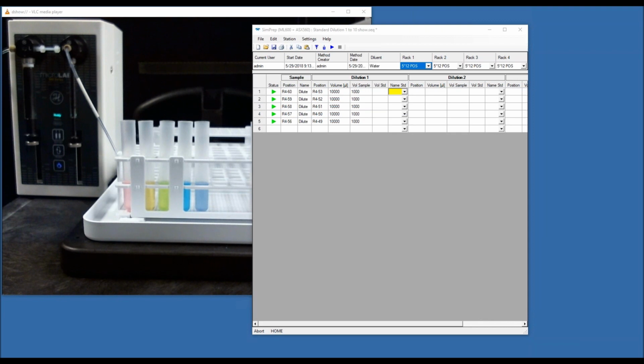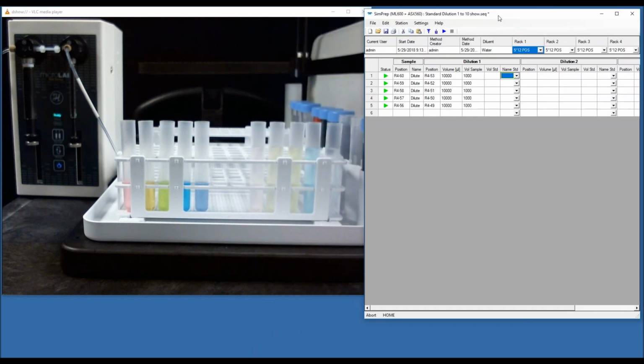Another question is, what is the time per sample? This is a pretty common question, and it really varies. Again, it's up to the user to some extent. A standard 1 to 10 dilution, like we showed here, typically takes somewhere around 30 to 35 seconds. For dispensing, it's more like 15 seconds, 10 seconds, depending on how much you're dispensing. The greater the volume, the greater the time. So that's up to the user.